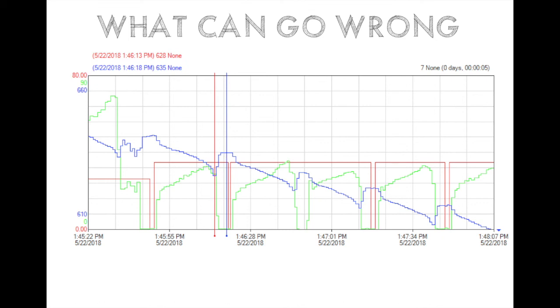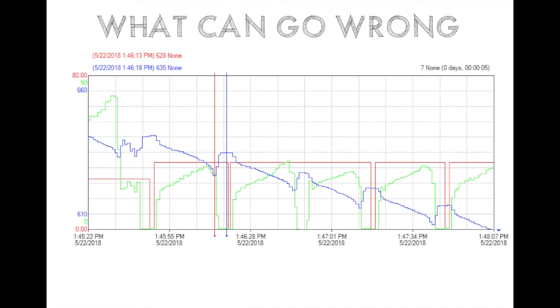So when the K-tron sees this jump in weight, it thinks it's going into a filling mode. So it jumps into what is very similar to a volumetric mode. And while it's doing that, it sends the flow rate to an absolute constant amount, which it has to make an assumption if that's right or not. It may or may not be right, and the fact that we're in this mode for so long means that something is definitely wrong and it's probably adding the wrong amount.